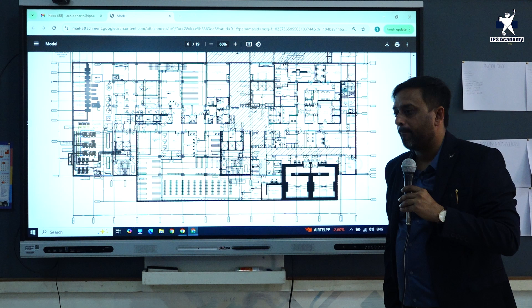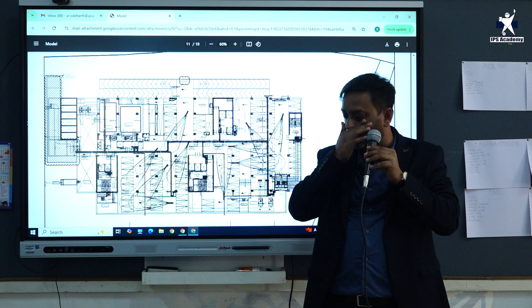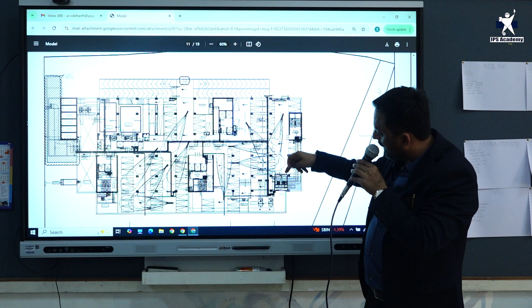Can you talk a bit about the service entrances for staff and services? Definitely, let's go to B1. If you see these fan directions, the basement is always divided into minimum 2 zones for the ventilation system. Earlier we used axial fans only with heavy ducts to balance fresh air or exhaust, but these are jet fans. The 2 zones are divided, shown in 2 different colors - air gets pushed here and a fan throws it outside, and similarly these fans throw the exhaust out.